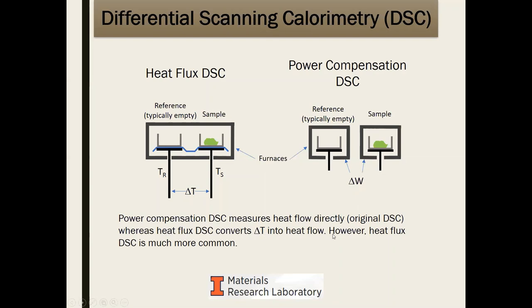The power compensation method measures heat flow directly and was the original DSC method. The heat flux DSC is much more common in laboratories today. Power compensation tends to be better for high heating rate experiments — above about 100 degrees per minute, you tend to be limited to power compensation. Heat flux DSC, being based on the older DTA method, actually handles higher temperatures overall. Both methods can obtain essentially the same data with appropriate calibrations. With advances in technology, those differences are getting smaller.